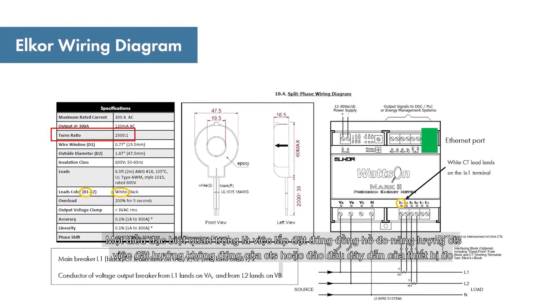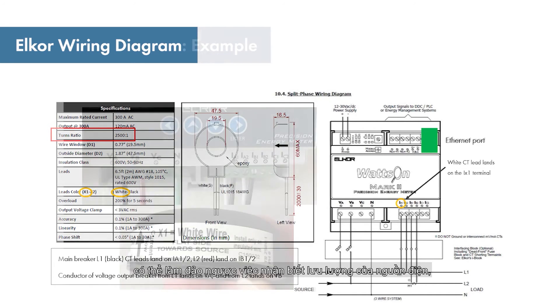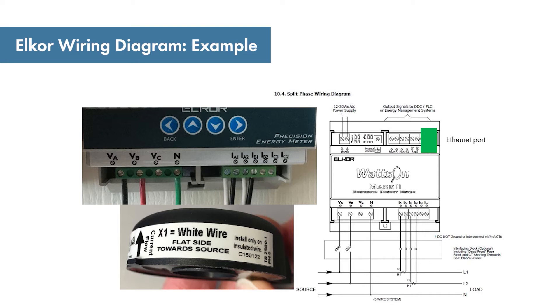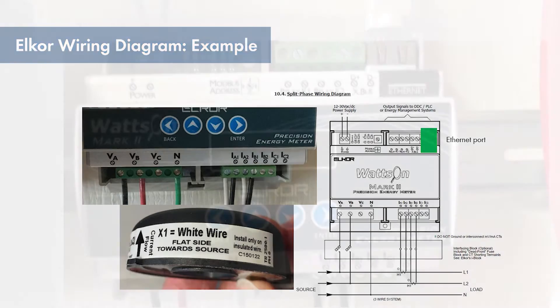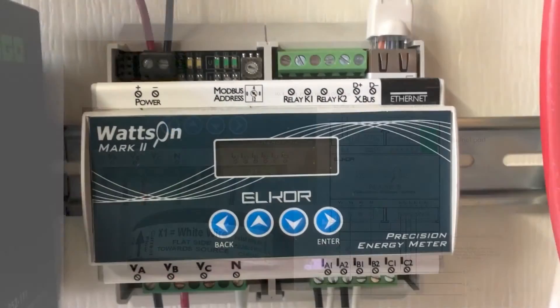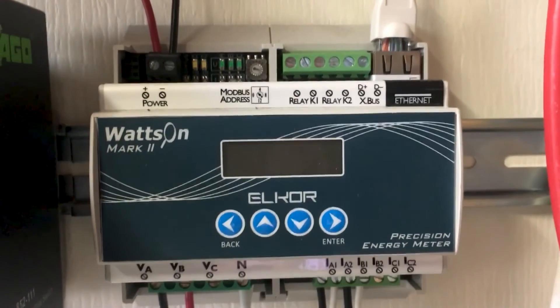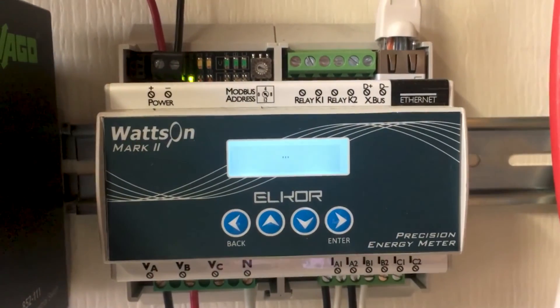Of particular importance is the correct installation of the energy meter CTs. Incorrect orientation of the CTs or reversal of the leads on the meter terminals can reverse the sign of power flow. For correct power measurement, verify that the voltage reference for phase A is connected to the same phase that is measured by the CT wired to the phase A current terminals. Once the meter is correctly wired, it can be powered on.